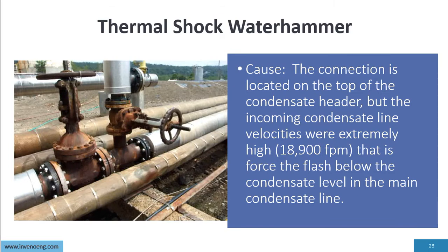Here's another one on thermal shock Waterhammer, and this connection location is the top of the header, which we said before is really what we want, connected into the top. However, the incoming condensate line velocities were like 18,900 feet per minute, which was really taking the flash steam and pushing it underneath the water level, and thus the bubble would collapse. Remember, we want condensate lines at 4,500 feet per minute. And this results in Waterhammer.